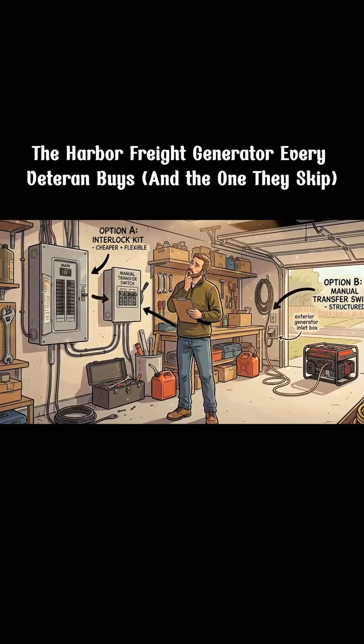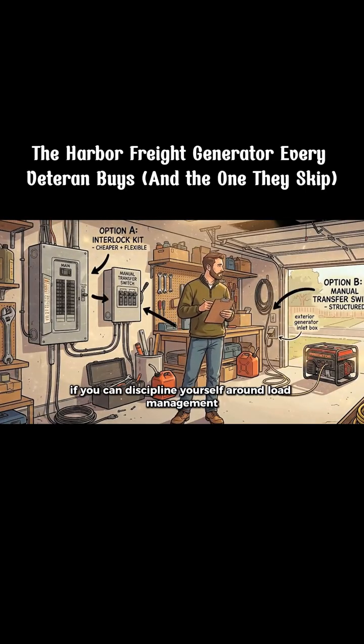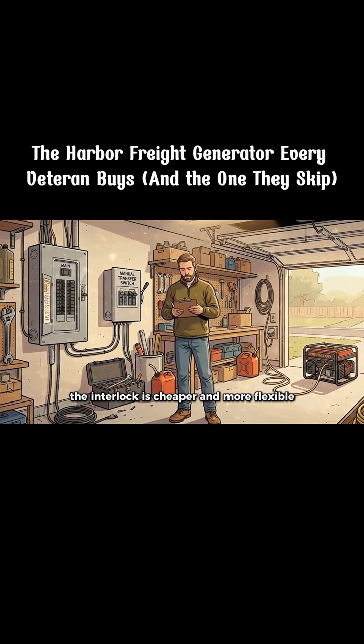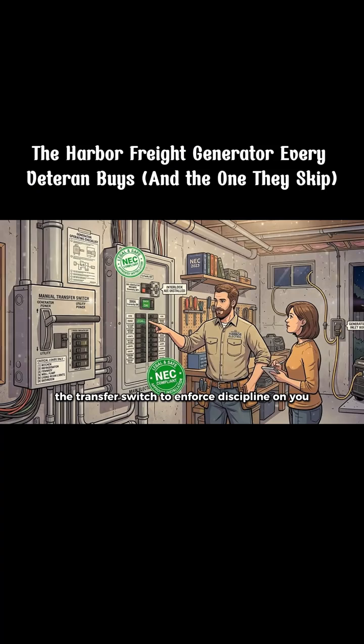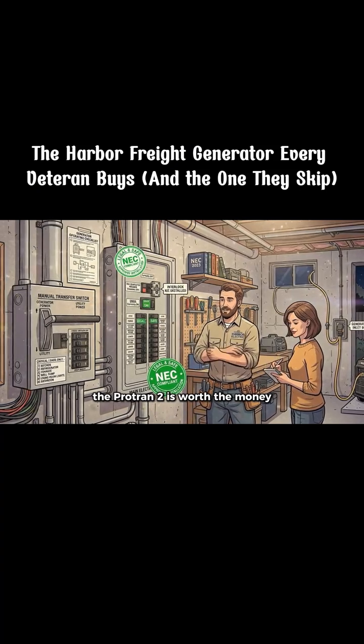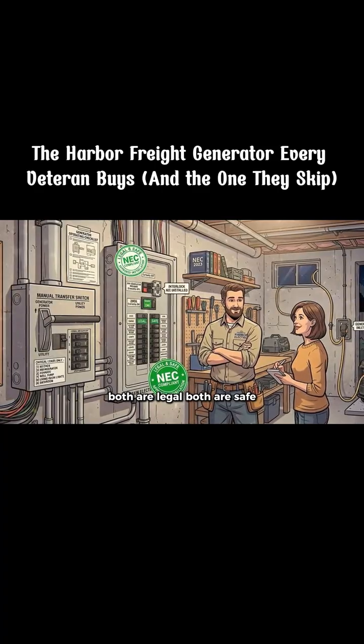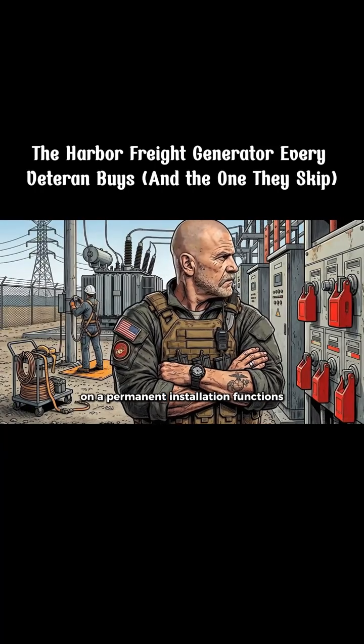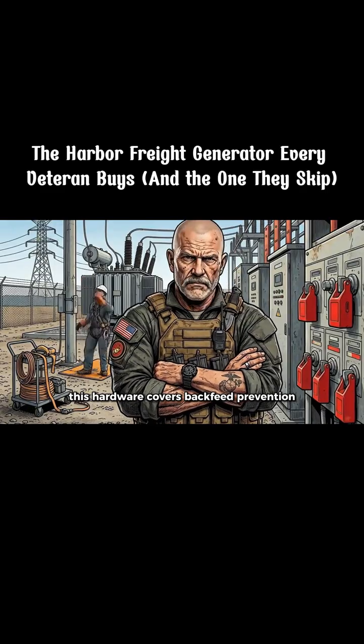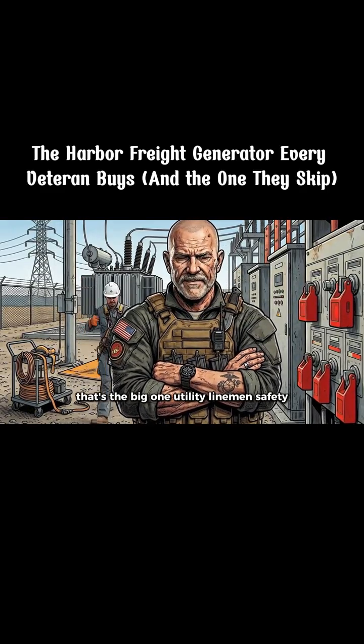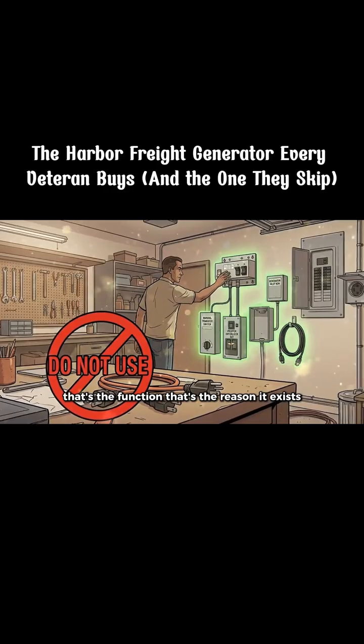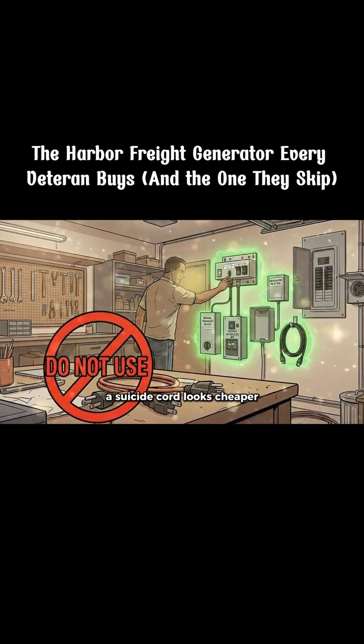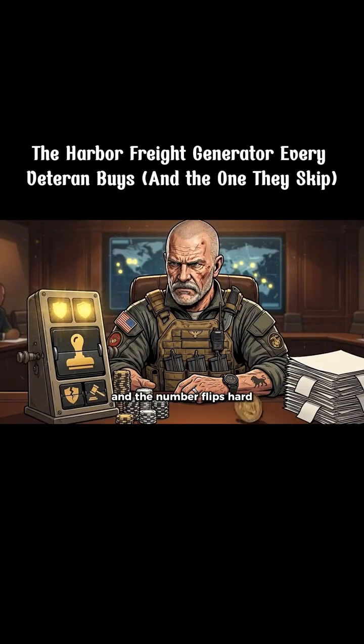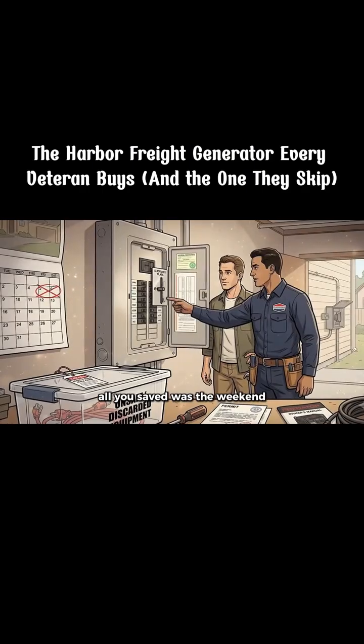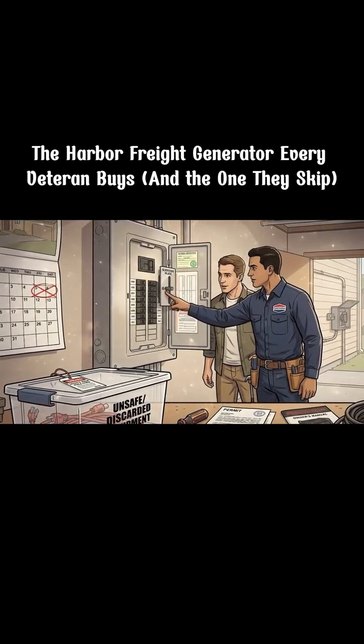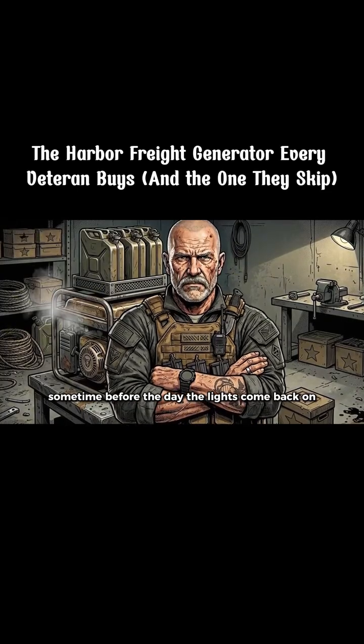Which one do you want? If you can discipline yourself around load management, the interlock is cheaper and more flexible. If you want the transfer switch to enforce discipline on you, the ProTran 2 is worth the money. Both are legal. Both are safe. Neither is optional on a permanent installation. Functions this hardware covers. Backfeed prevention. That's the big one. Utility lineman safety. That's the function. That's the reason it exists. A suicide cord looks cheaper. Include your legal exposure in the pricing and the number flips hard. All you saved was the weekend to install the interlock properly. That weekend arrives sometime before the day the lights come back on.